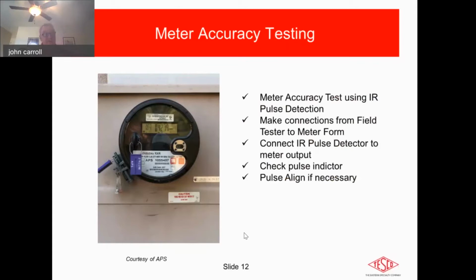The meter technicians generally have their routine. They know what to look for. But the meter connections from the field test to the meter itself, typically on an IR pulse detector. We also have pulse detectors that not only pick up on the front there from the magnetic ones, we have ones which we actually have designed specifically for any pulses that come out the top of the meter through a light pipe that might run down the back of the meter base itself. And we can also share information on that one too. It's very specifically for that type of particular meter.